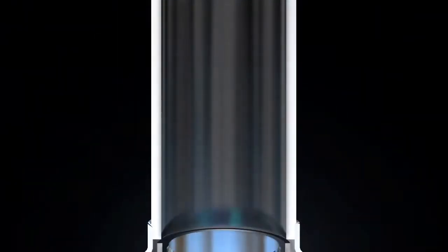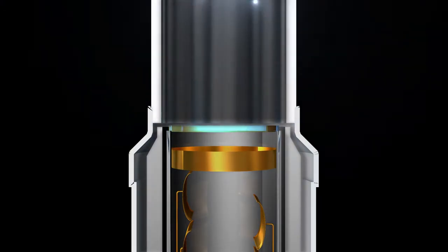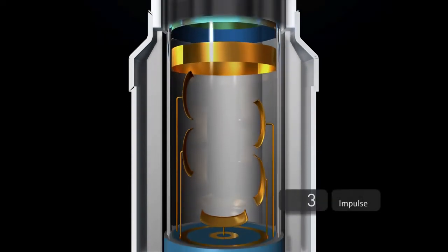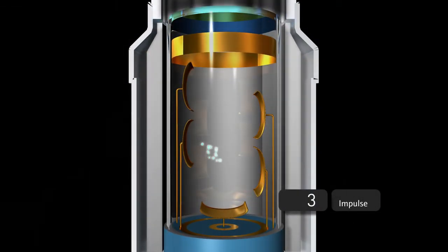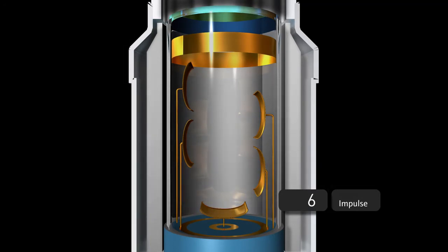As this occurs, a gamma photon of the scintillator is converted into a flash. This flash is transmitted to the photomultiplier in the scintillator, as is the case in a glass fiber line. In the photocathode, the flash is converted into a very low charge, which is then amplified to an evaluable current pulse in the photomultiplier. The same is then processed to become a measuring signal.